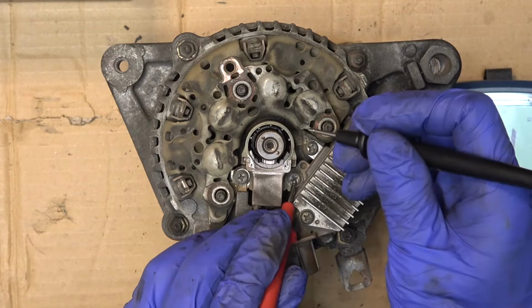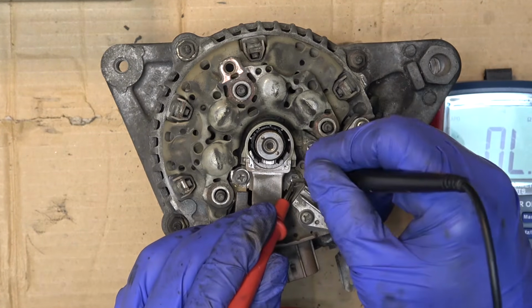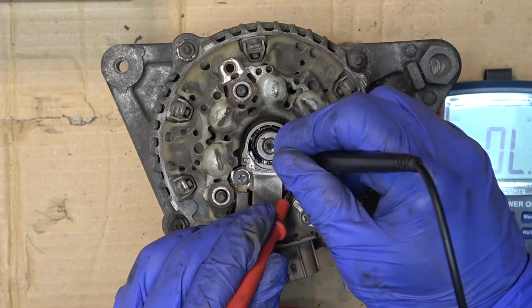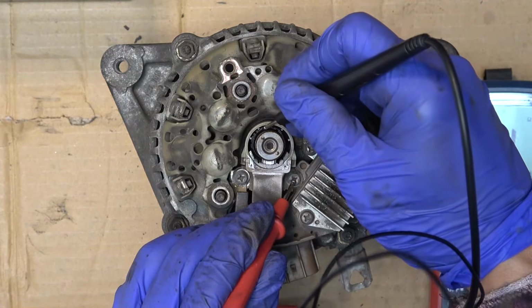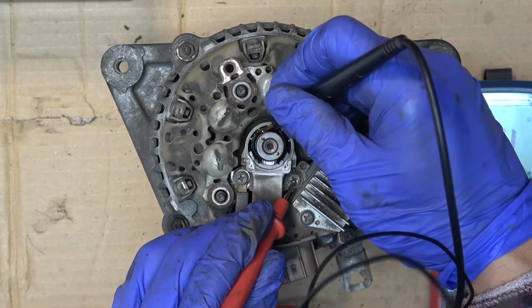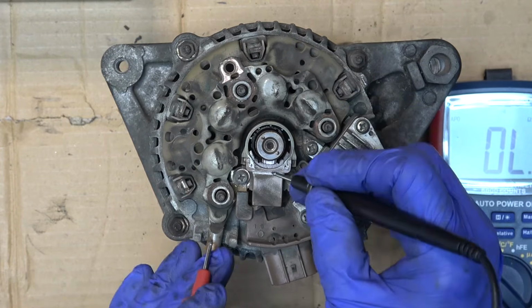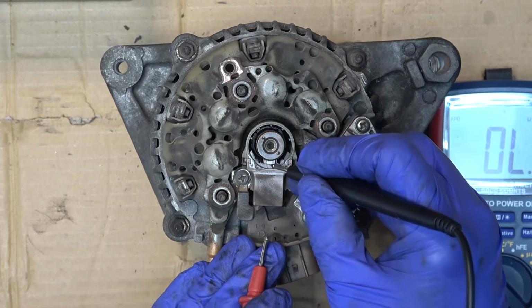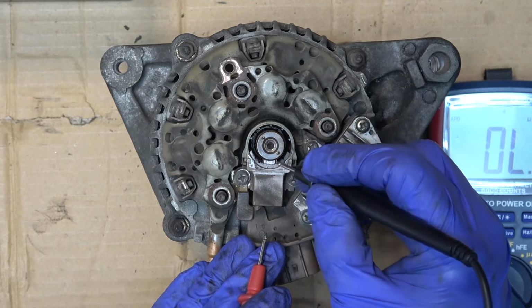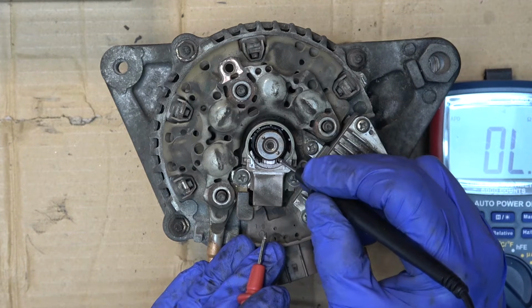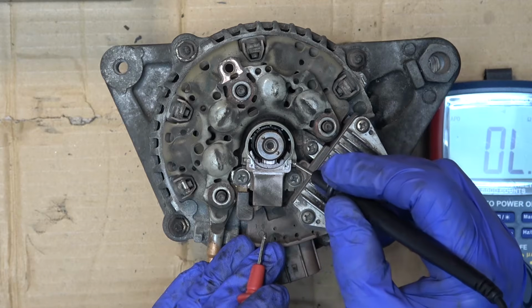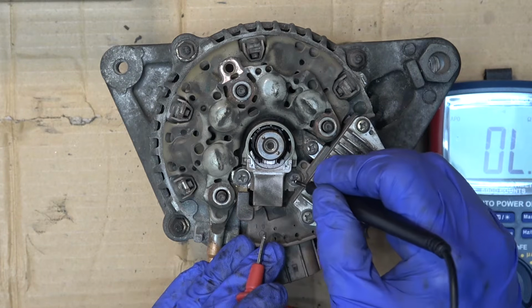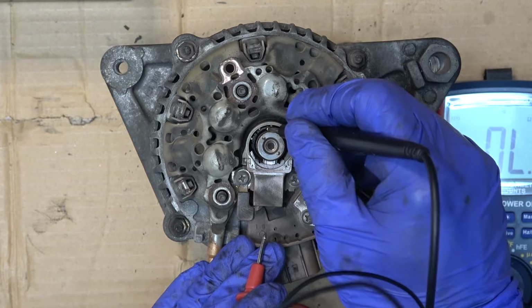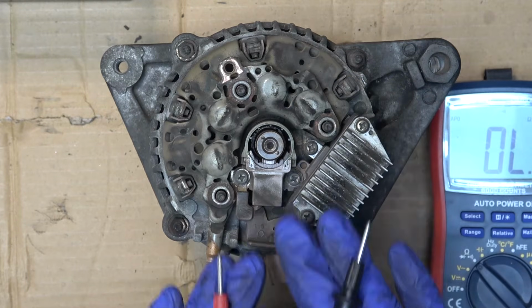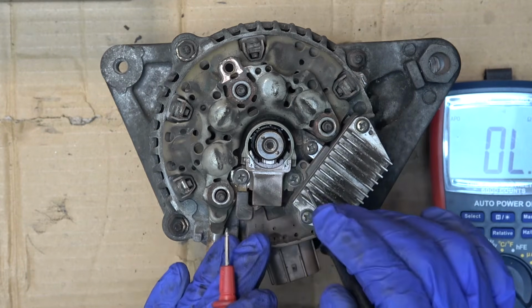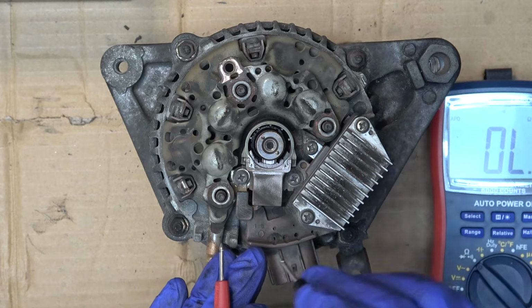Let me try this again. This should be continuous to the top brush, and that should be continuous to the top slip ring, and it's not beeping. That means this brush here on the top is too worn out, to a point where it's too short to touch the slip ring, and therefore it's not continuous between here and the slip ring anymore, and there's no power being sent to the rotor from the regulator anymore.